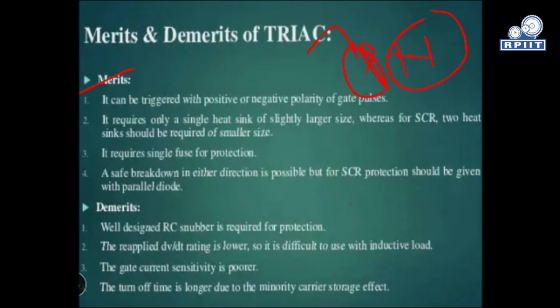Next, it requires only a single heat sink of slightly larger size. In an ordinary SCR arrangement we need two heat sinks of smaller size, but here we need only one larger heat sink. That is the main advantage. It also requires only a single fuse for protection, rather than the conventional arrangement of SCRs.